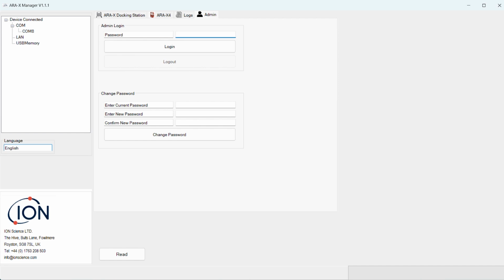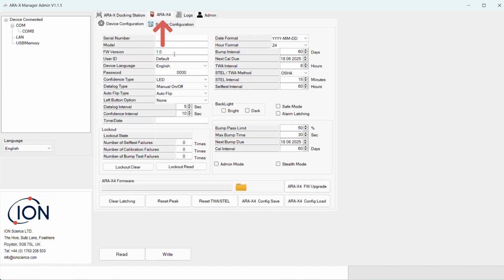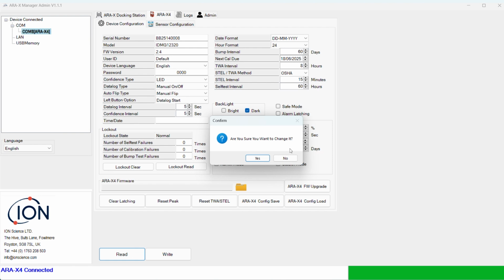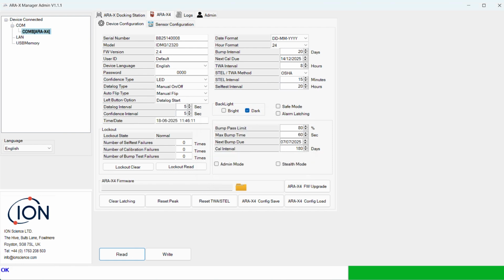To change or swap out the sensors on your ARA-X4, first open the ARA-X software and log in as admin. You'll see Admin confirmed here. Select the ARA-X4 tab at the top of the screen. Then, in the left-hand menu, select the COM port and click the Read button at the bottom of the screen. This will bring up the most recent information from the ARA-X4 device.